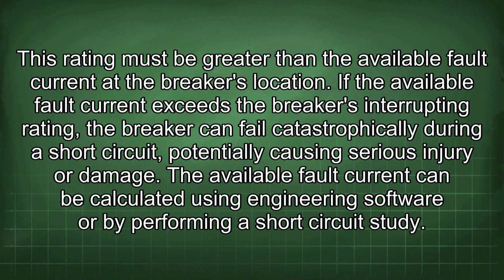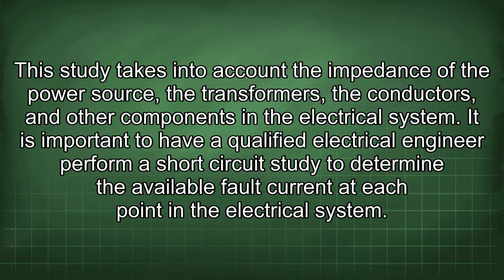The available fault current can be calculated using engineering software or by performing a short circuit study. This study takes into account the impedance of the power source, the transformers, the conductors, and other components in the electrical system. It is important to have a qualified electrical engineer perform a short circuit study to determine the available fault current at each point in the electrical system.